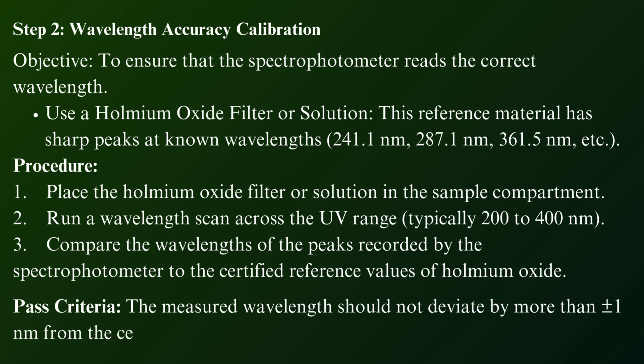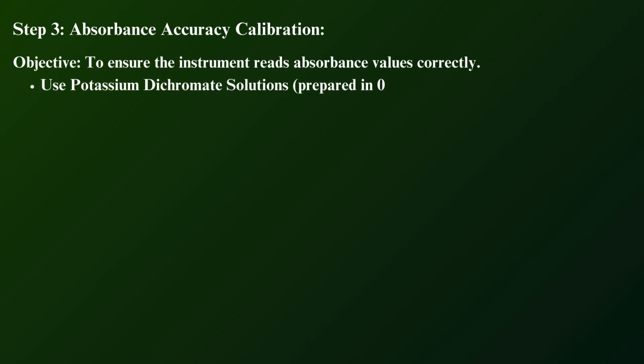Step 3: Absorbance accuracy calibration. Objective: To ensure the instrument reads absorbance values correctly. Use potassium dichromate solutions as the reference standard.